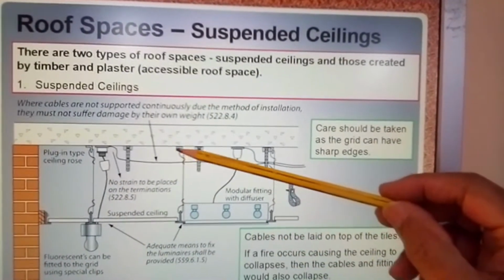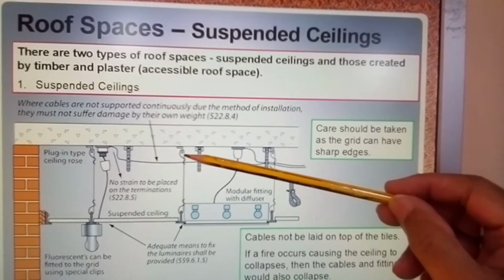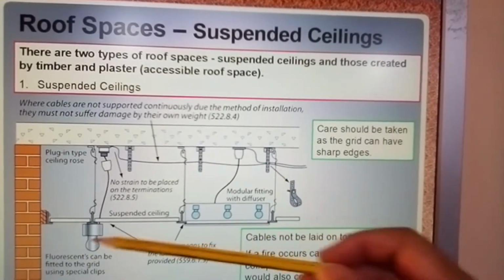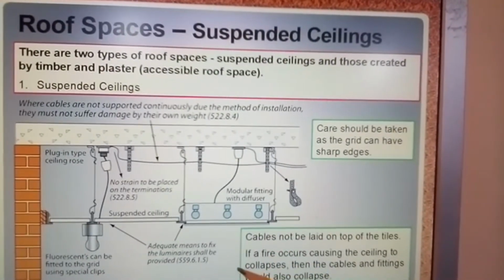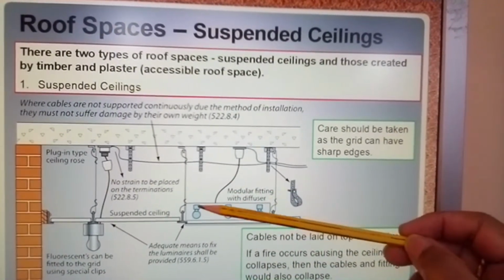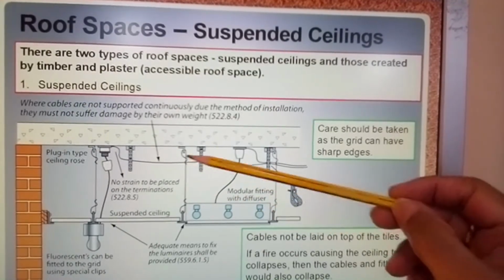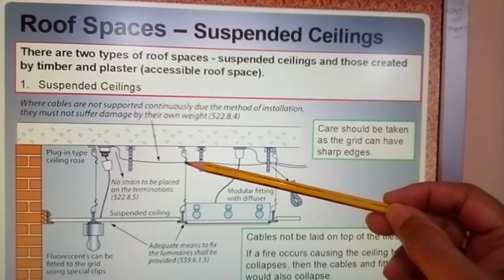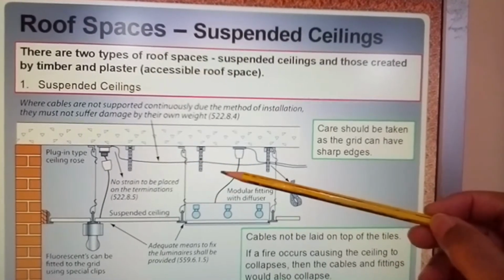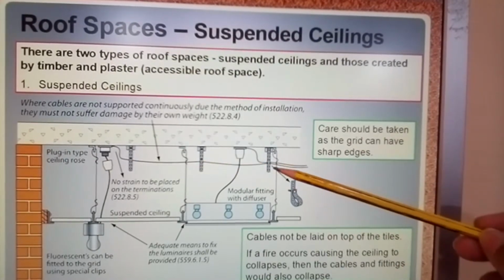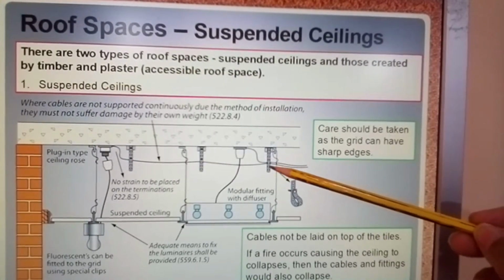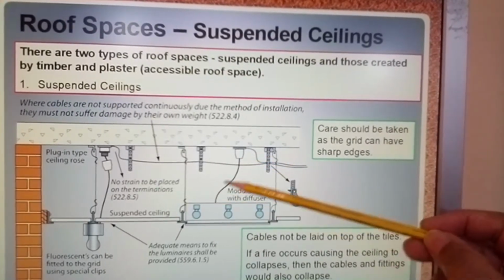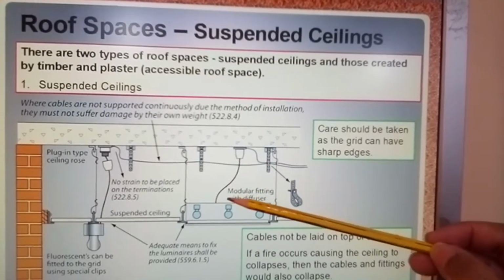And again, here you have a different type of system here. Now remember that when you put this in place, it must be secured, because you do not want this unit or this unit falling or dropping down because it came unlatched, okay. So it must be secured. Normally these are bolted up and clamped with a clamp, okay, and secured. Your cables can be run as you like onto something soft or any mechanism that does not cause damage to the cable. And here you can see that this cable here has no strain on it, okay.